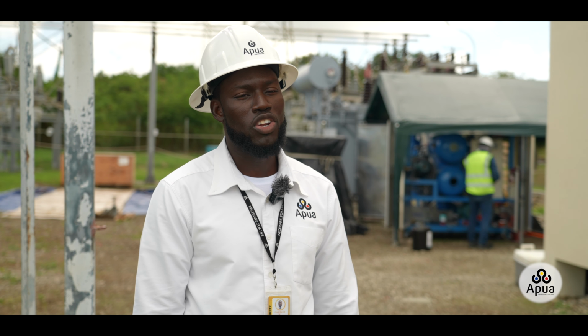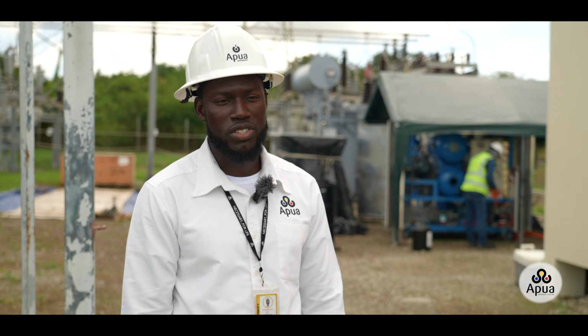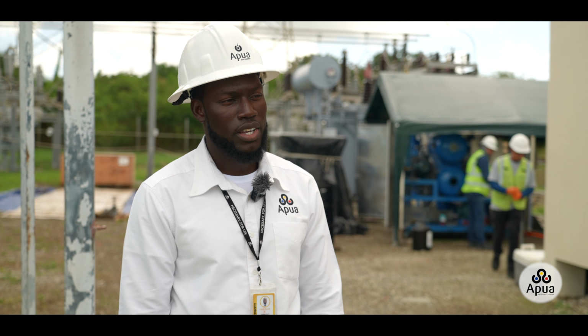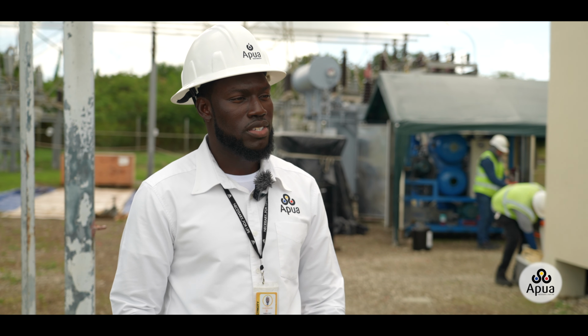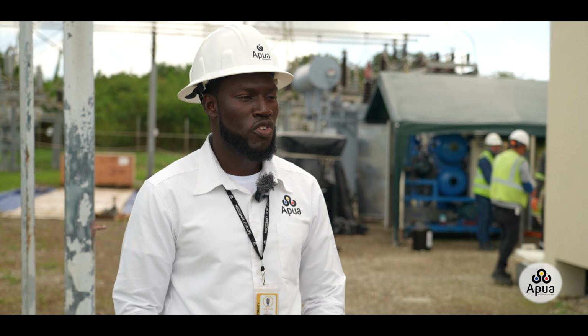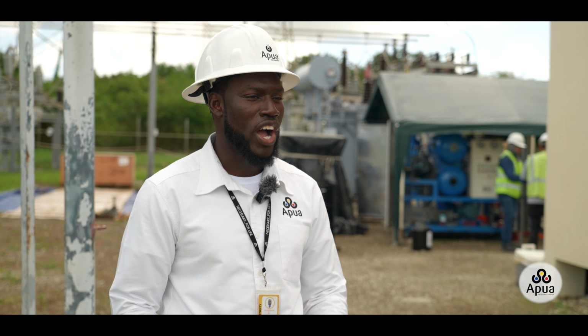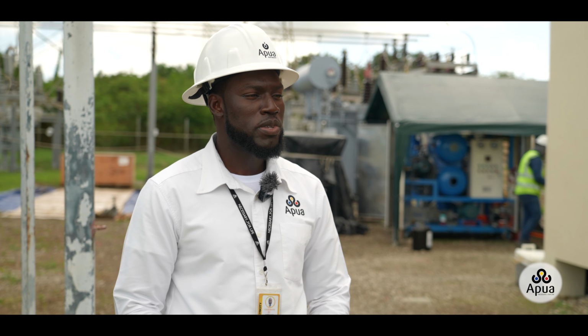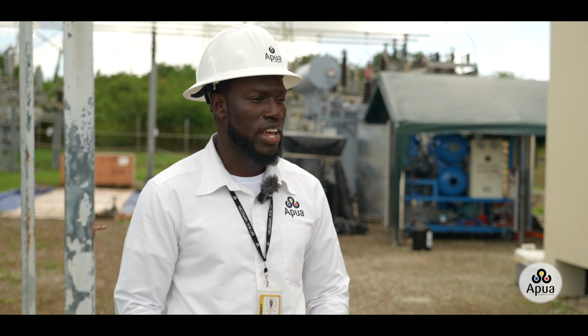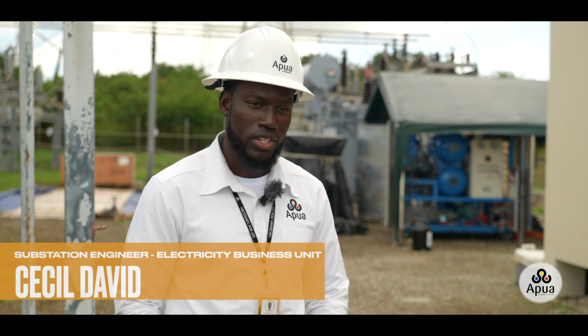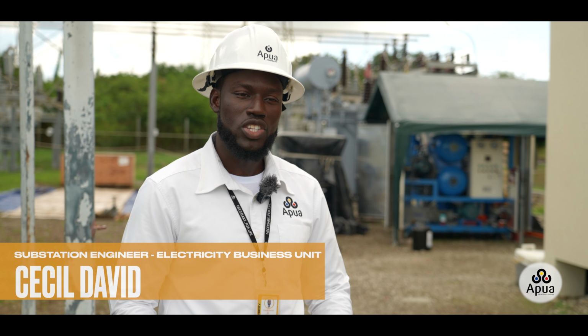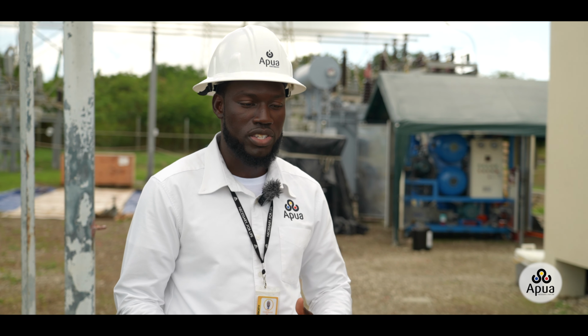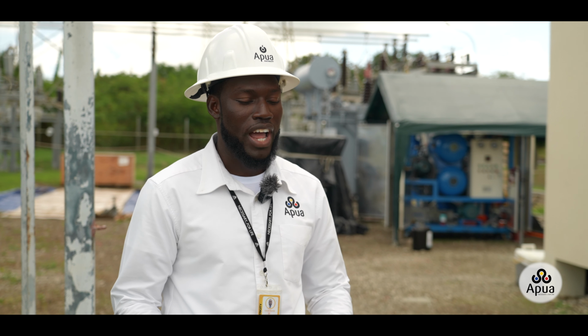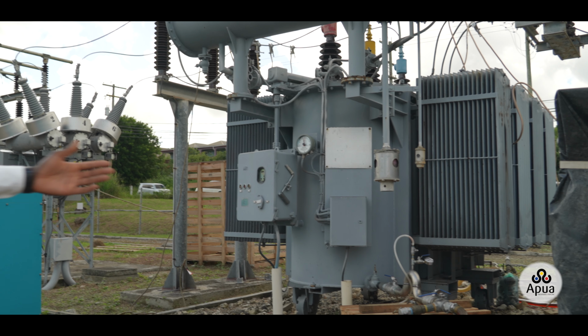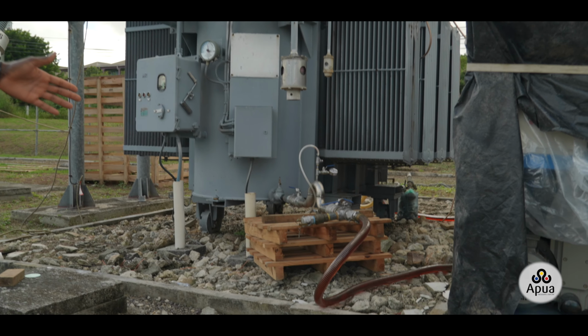We are doing what's called an oil reclamation process on the Belmont transformer that feeds Belmont substation. The oil process is to purify the oil, remove contaminants, and try to rejuvenate or add life back to the oil. The purpose of the oil in the transformer is to add a level of insulation and cooling, because of course, the core heats up during the process of the transformer operating. And the oil in itself acts as a cooling element through convection, and also it adds a level of insulation between the core, lamination, and all the other compartments of the transformer.